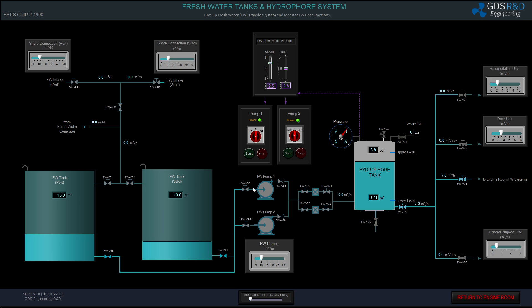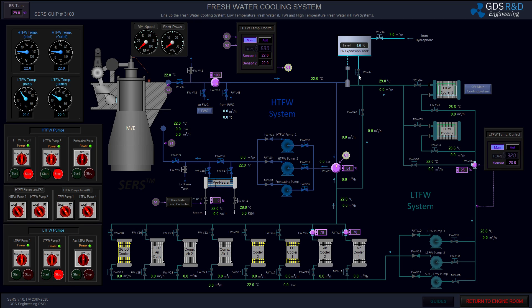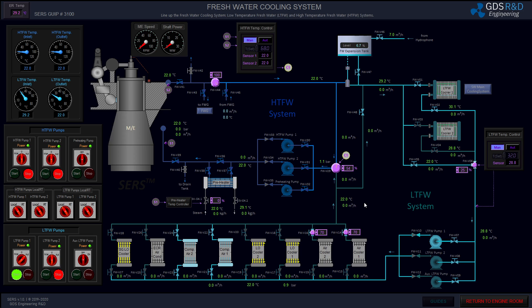I will feed the pumps from both tanks — port and starboard — using filter number one. I will switch the pump to auto position. I will open the outlet valve of the fresh water expansion tank so I can supply fresh water to my pumps and all the coolers. I will start the air compressors first, opening inlet and outlet valves of the compressor coolers. I will operate the low temperature fresh water pump in automatic mode.